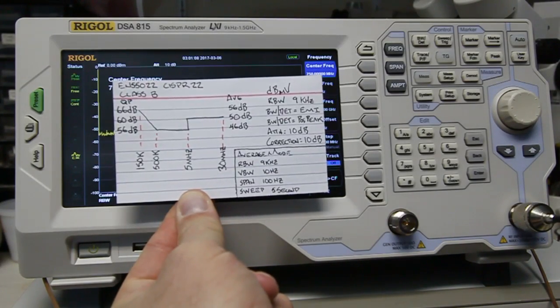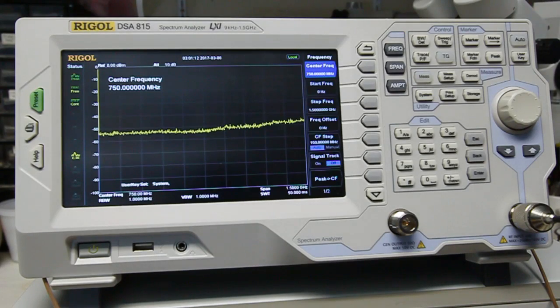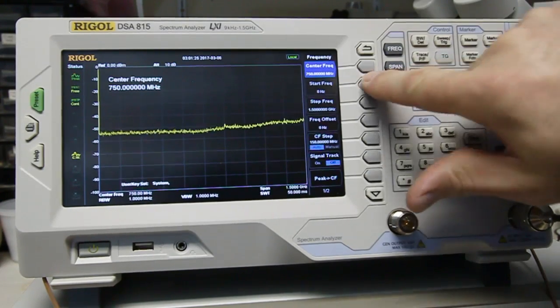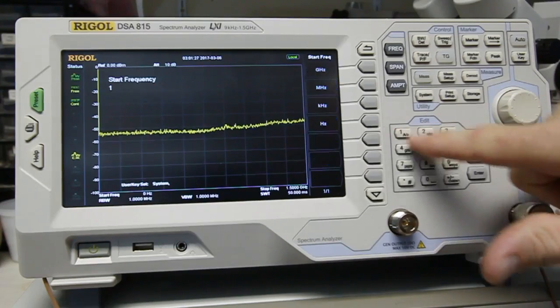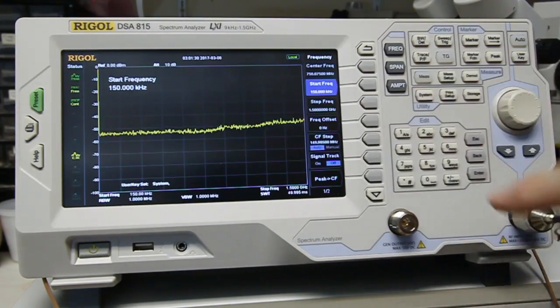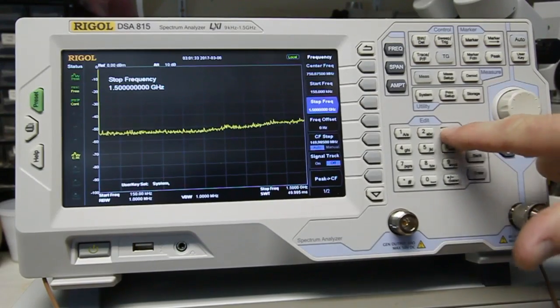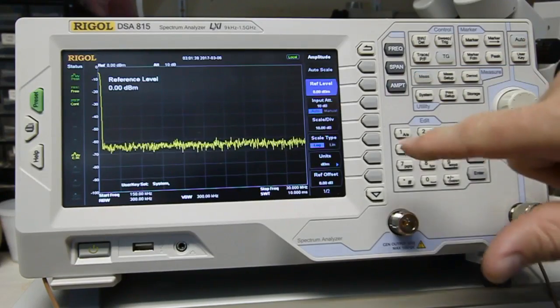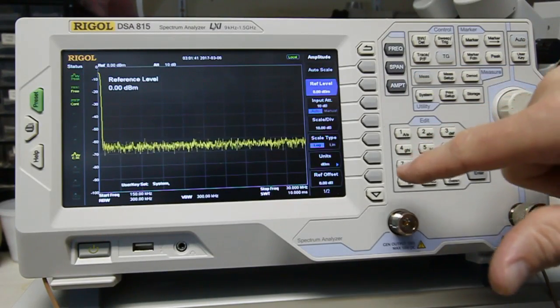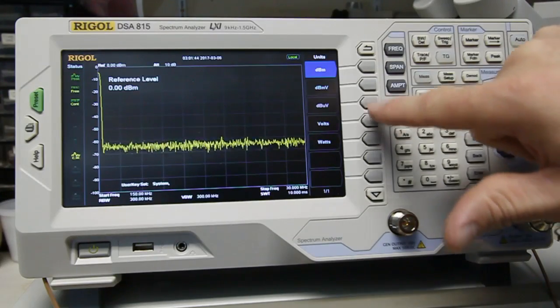Here's my little handy-dandy cheat sheet that I use. So the first thing that we're going to do is I'm going to set up the frequency bounds and what type of units we're going to use. The specification says that we start at 150 kilohertz and our stop frequency is 30 megahertz. Our amplitude is in dB microvolts.